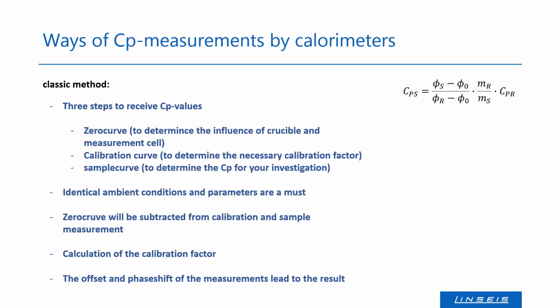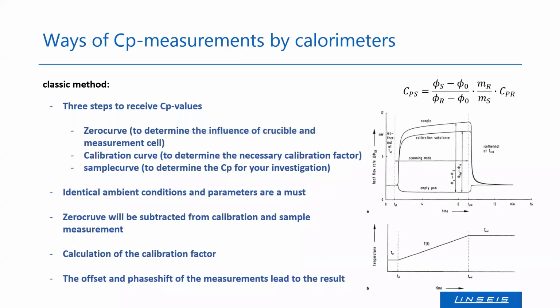What's important for these 3 measurements is that we need identical ambient conditions and parameters. So we need the same heating rate, in the best case the same temperature range, and also the same atmosphere and the same crucible. This is pretty important. The zero curve will be subtracted from the calibration and the sample measurement, and then we can calculate the calibration factor. So what are we looking at? We've got these 2 measurements with the correction measurement, and we look at the offset and the phase shift of our measurements. This is how we receive our CP. Here you can see on the right now the temperature profile at the bottom.